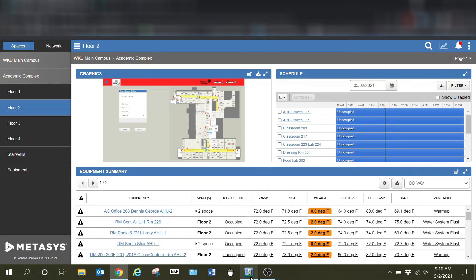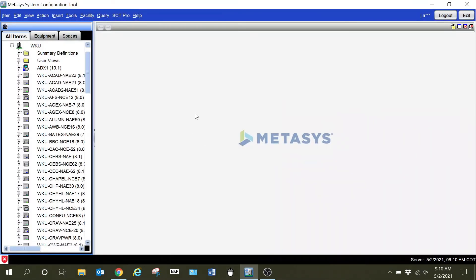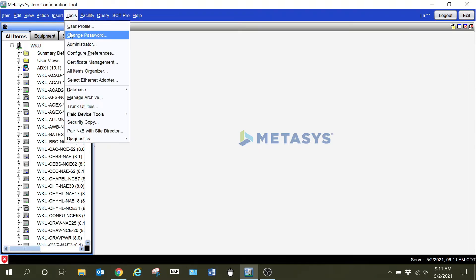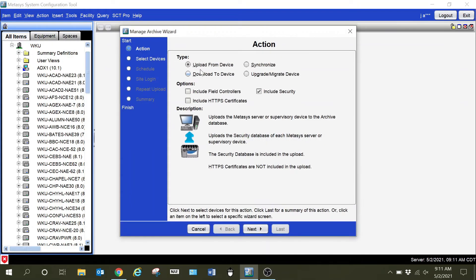The first thing that you're going to want to do is to become familiar with your SCT. This is where we're going to be doing a lot of work — setting up our spaces and all of that. One thing you want to remember when you do your synchronization to the server: talking with one of the JCI techs, it seems to work a little better for us. Instead of doing a download to the server, we will typically do a synchronization. When you go to your manage archive, it's going to give you the options to either upload or download.